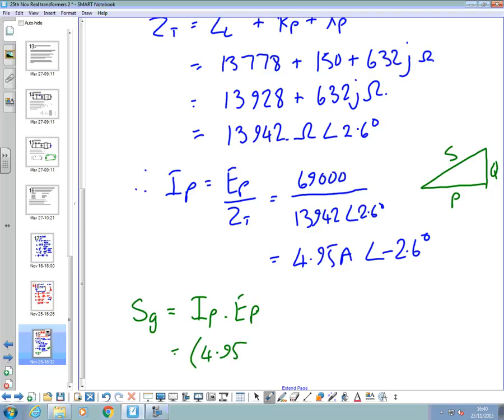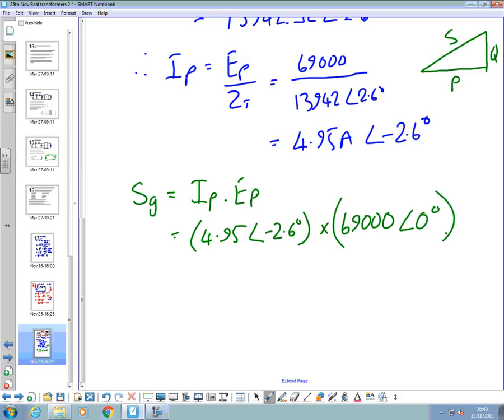That's 4.95 angle minus 2.6 times 69,000 angle 0. All agree with that? And I got 341,550 VA angle minus 2.6 degrees.